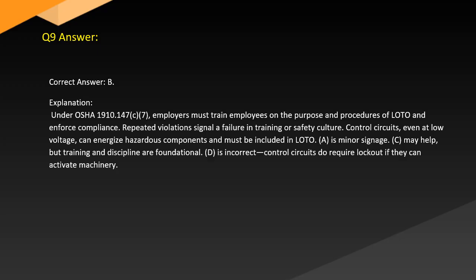Control circuits, even at low voltage, can energize hazardous components and must be included in LOTO. A is minor signage. C may help, but training and discipline are foundational. D is incorrect. Control circuits do require lockout if they can activate machinery.